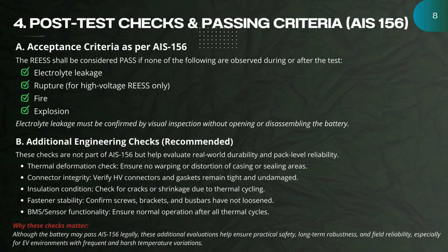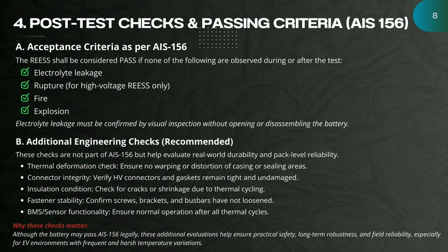Upon completion of the thermal shock cycles, the battery is evaluated in accordance with the AIS-156 acceptance criteria. The REESS passes the test if none of the following are observed: electrolyte leakage, rupture for high voltage REESS, fire, explosion. Electrolyte leakage is checked visually without opening the battery. Apart from the AIS requirements, additional engineering checks can also be performed to assess real-world durability, such as looking for casing deformation, connector integrity, insulation condition, fastener stability, and proper BMS operation.